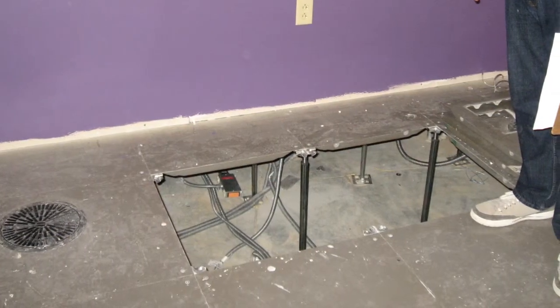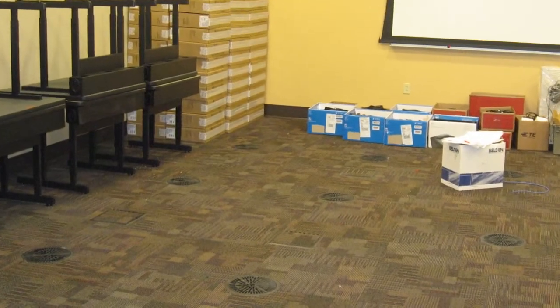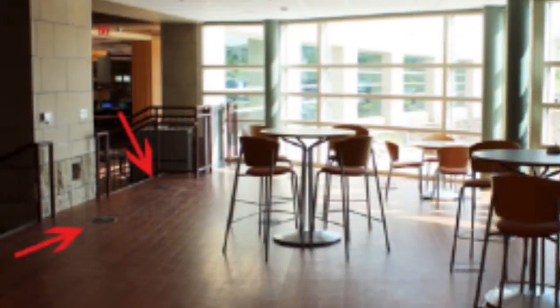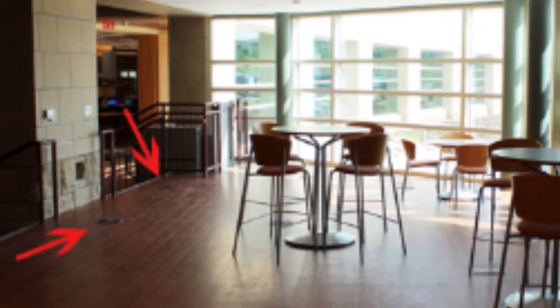The UFAD system has air diffusers located in the floor, delivering air from below, with power and data the same way. So as furniture or equipment moves, it's simply a matter of relocating those devices to coordinate with the new layout. There are three advantages for the owner with the UFAD system: flexibility for the owner's requirements, comfort for the occupants, and energy savings in terms of usage.